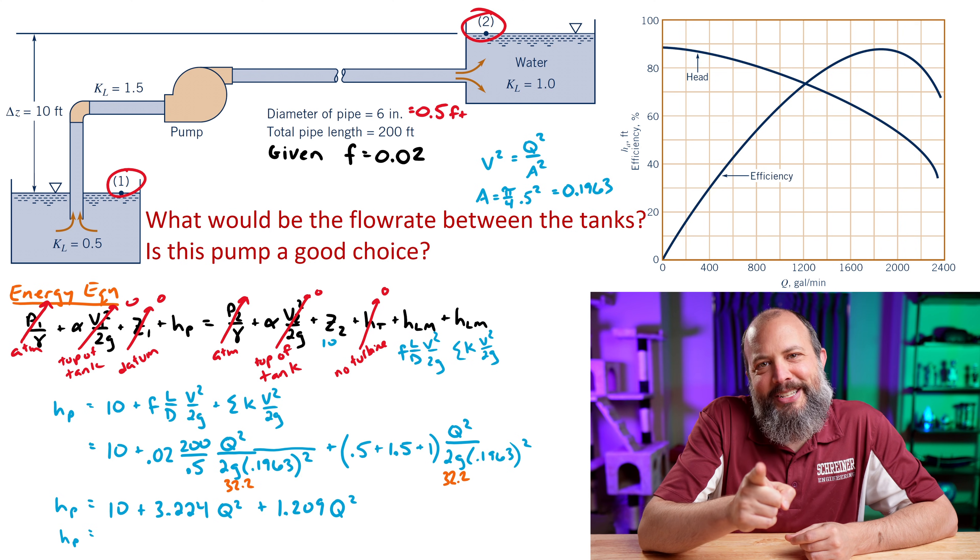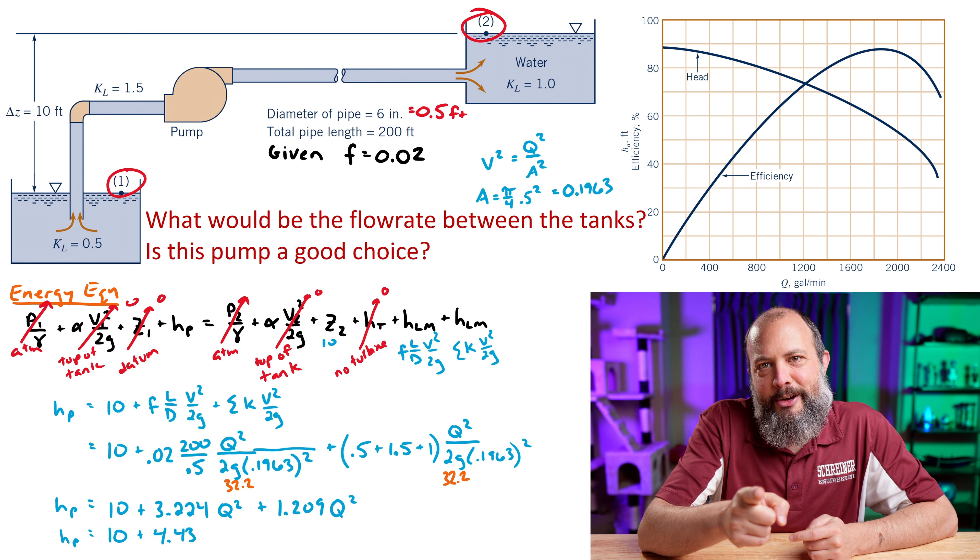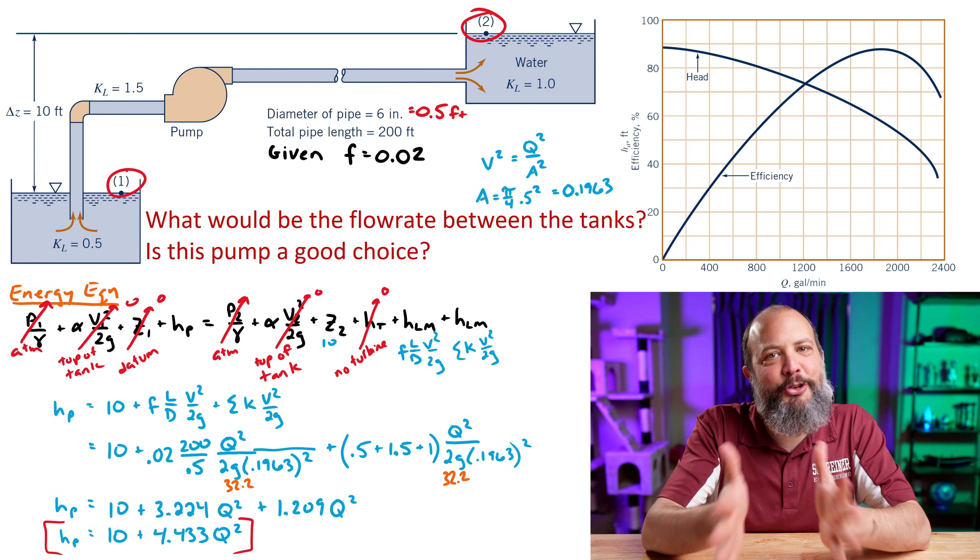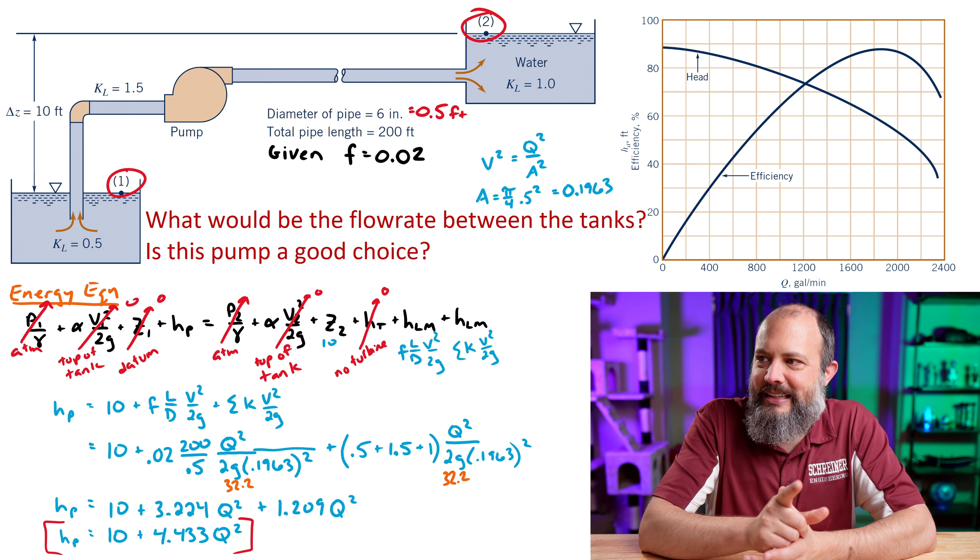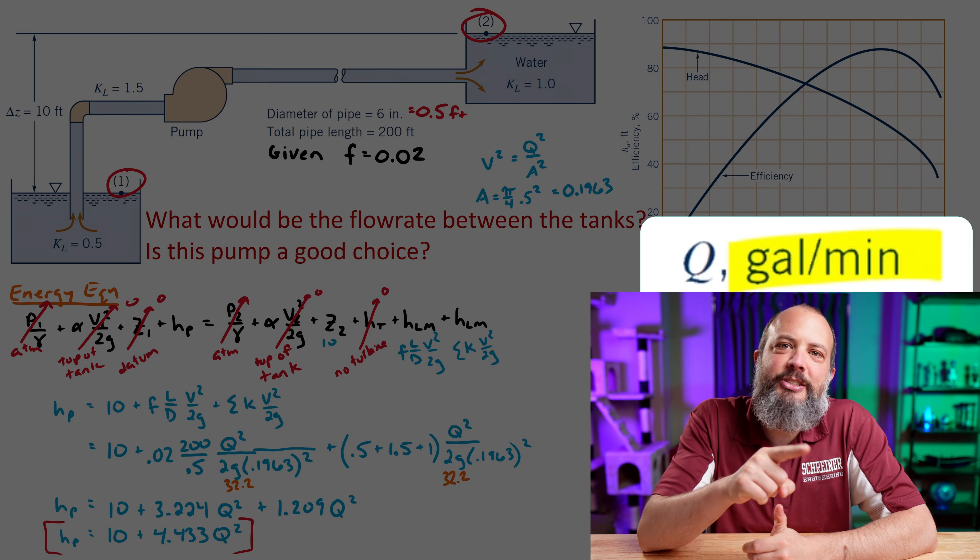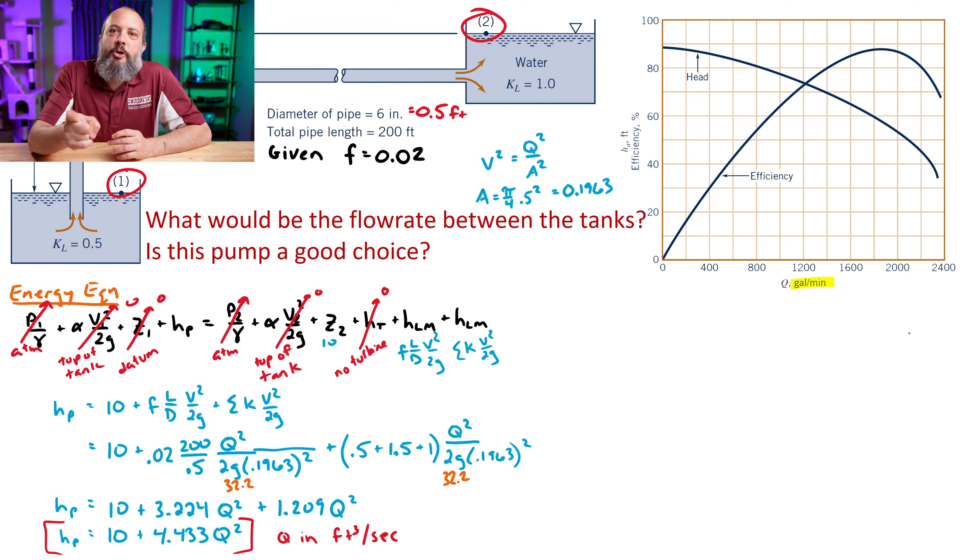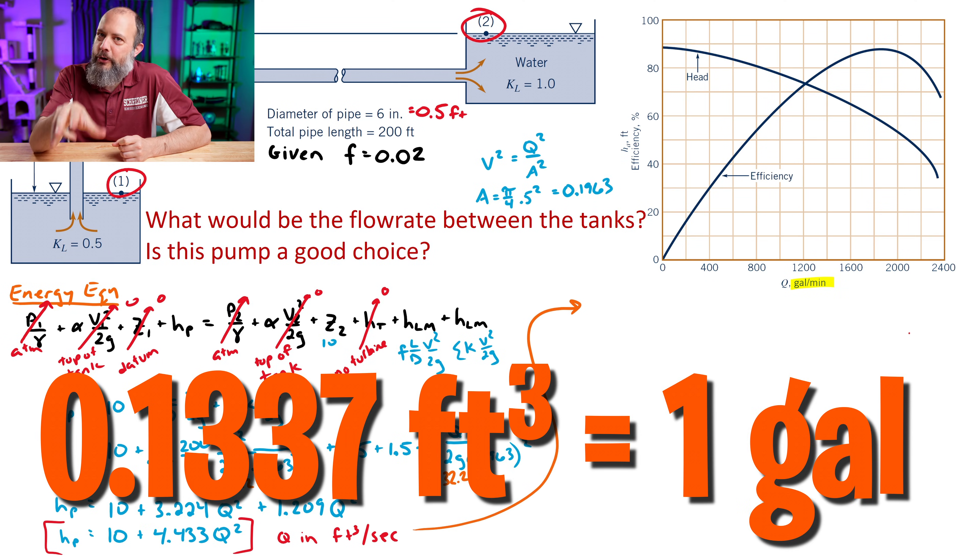But what units is this value of Q in right now? My velocity was in feet per second, and my area was in feet squared, so my Q is actually in cubic feet per second, which does not match the x-axis of the plot, which is in gallons per minute. And every online gamer who's not a noob will remember that the conversion from gallons to feet cubed is going to be 0.1337. So 0.1337 is leet, right? That is the conversion. That's how many cubic feet are in one gallon.